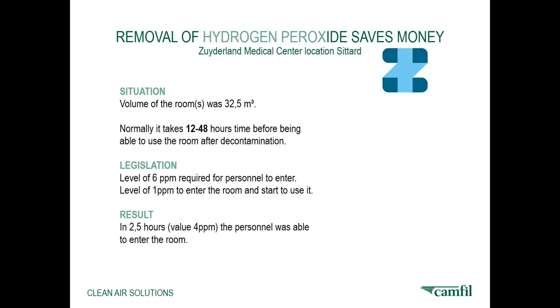In this example, I'll describe how removal of hydrogen peroxide saves money at Zuyderland Medical Center. Hydrogen peroxide is being used to decontaminate nursing rooms, recovery rooms, operating theaters, etc. This process takes about 1 hour, depending on the size and the contaminant. In this particular case, we had a room volume of 32 cubic meters, and normally it takes 12 to 48 hours before being able to use the room after decontaminating, according to legislation demands.